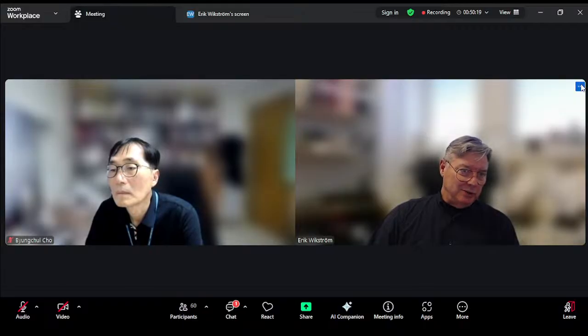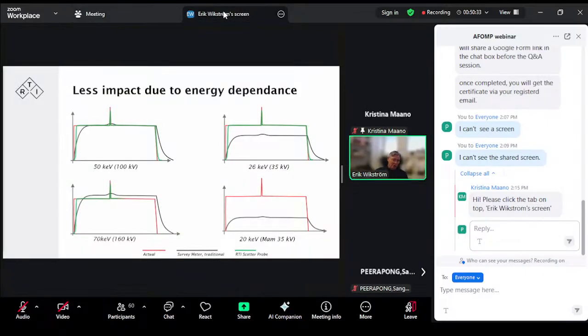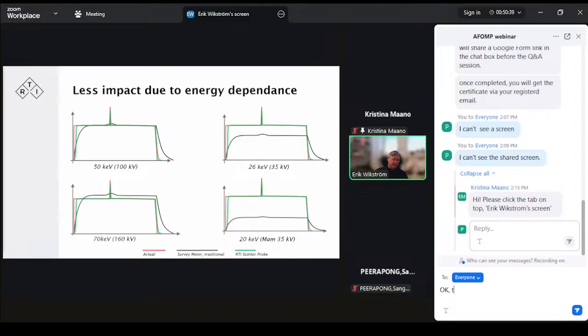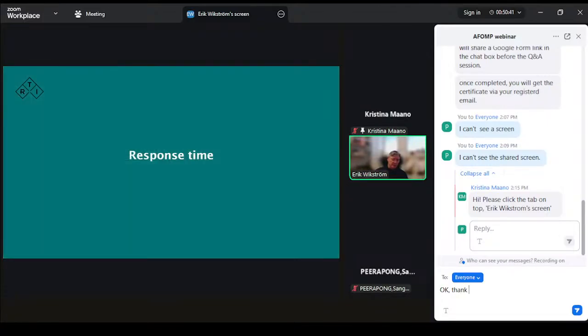And what does that bring then? Well, we saw these curves first, and here we see a better response time, so we track it more easily. Even if there is a bump in the road, we can monitor that, and we come up to the right value. Same thing here. It matches all along the waveform for all energies in the diagnostic imaging range.